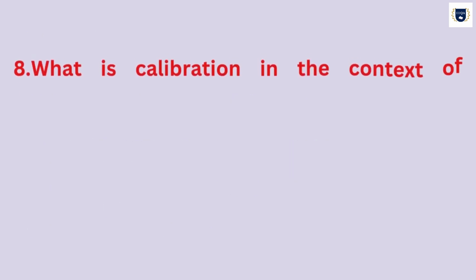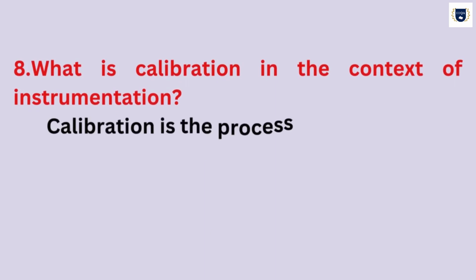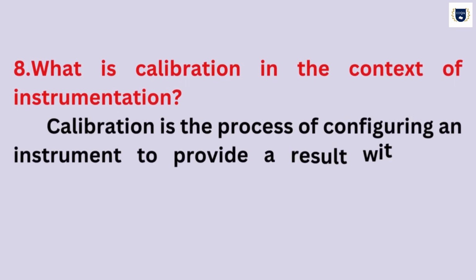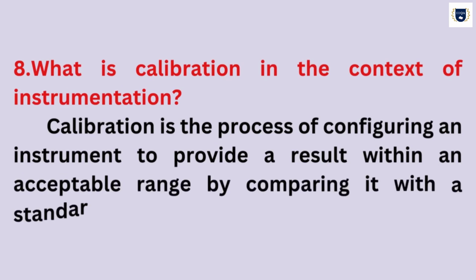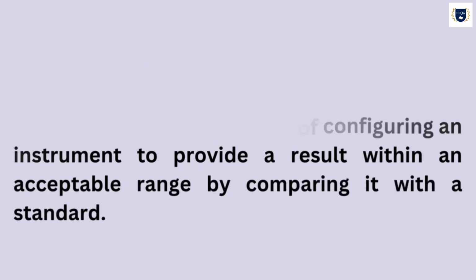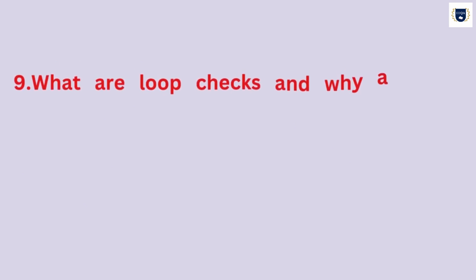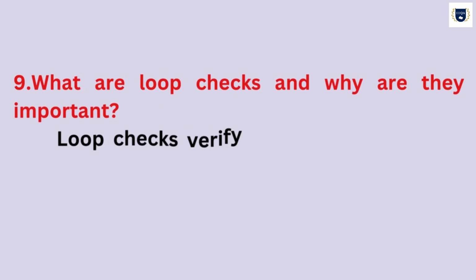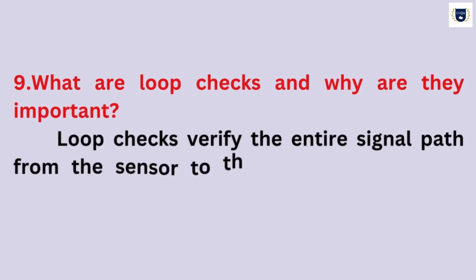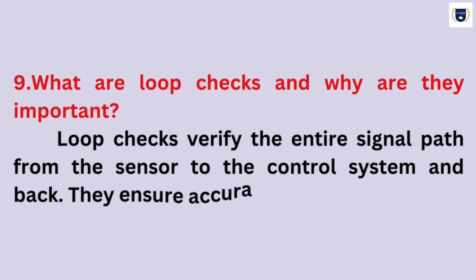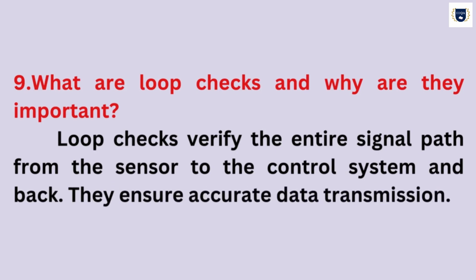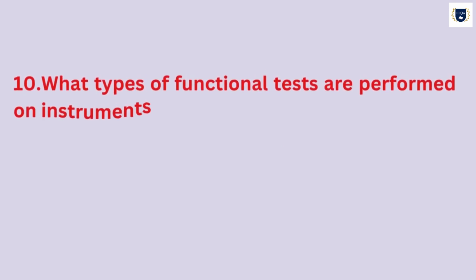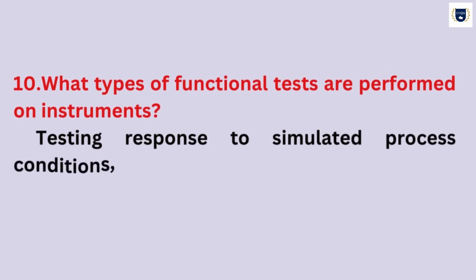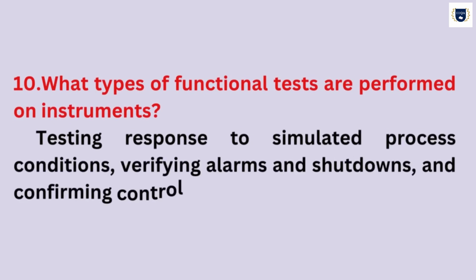What is calibration in the context of instrumentation? Calibration is the process of configuring an instrument to provide a result within an acceptable range by comparing it with a standard. What are loop checks and why are they important? Loop checks verify the entire signal path from the sensor to the control system and back. They ensure accurate data transmission. What types of functional tests are performed on instruments? Testing response to simulated process conditions, verifying alarms and shutdowns, and confirming control loop functionality.